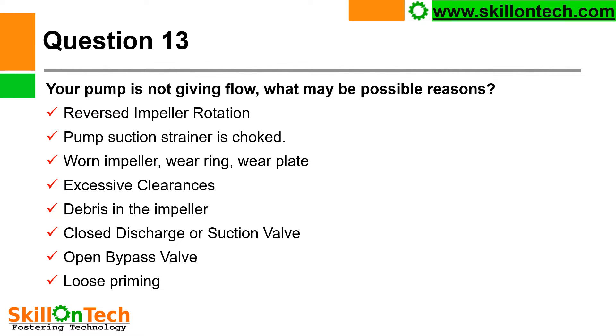Worn impeller, wear ring, or wear plate. Excessive clearances in the impeller wearing ring or impeller casing ring — so there will be leakage. Debris in the impeller: if small debris enters the impeller, it will also disturb the discharge. Closed discharge or suction valve: if your discharge or suction valve is closed, your pump will not give flow.